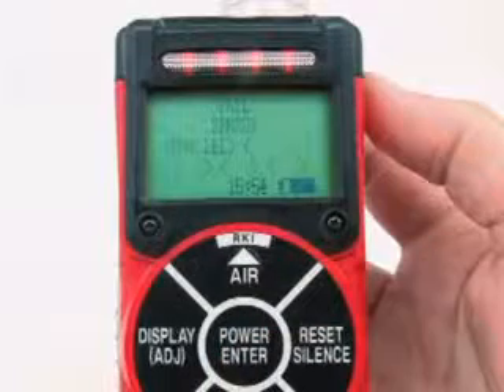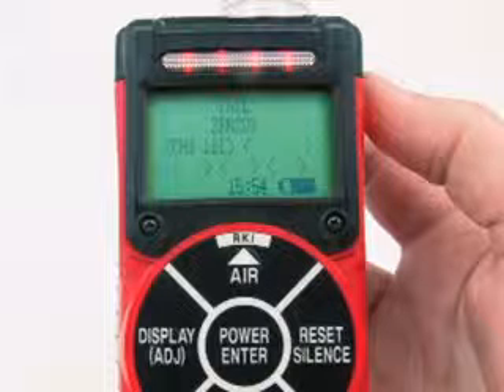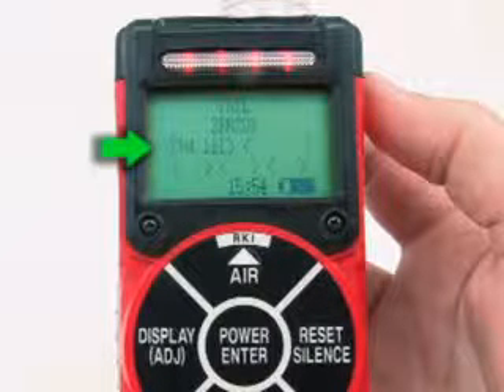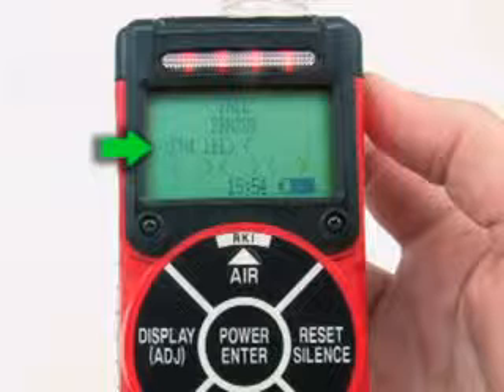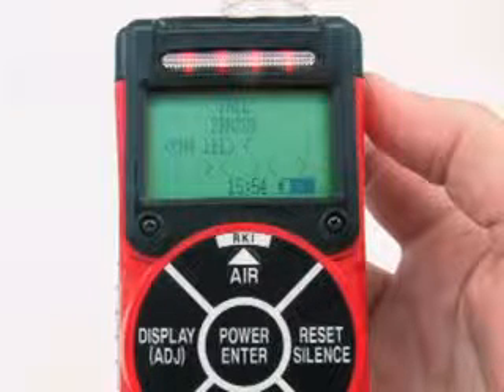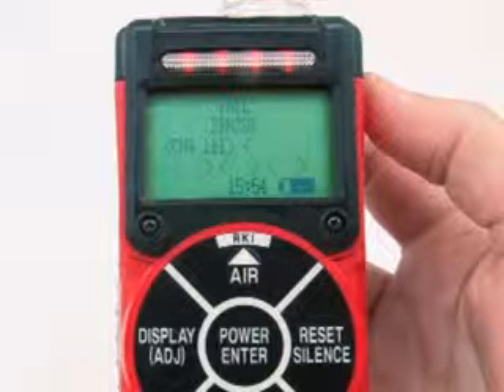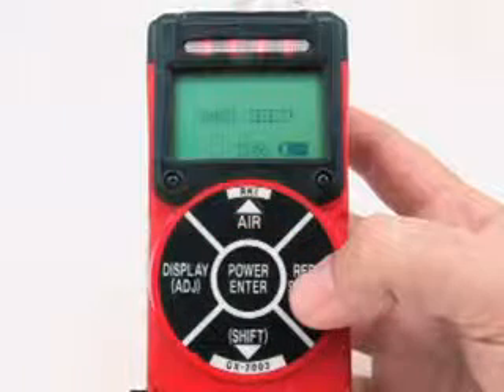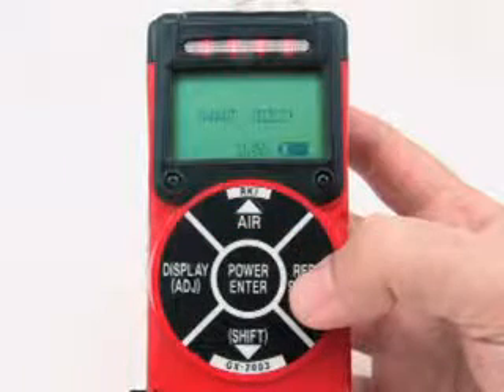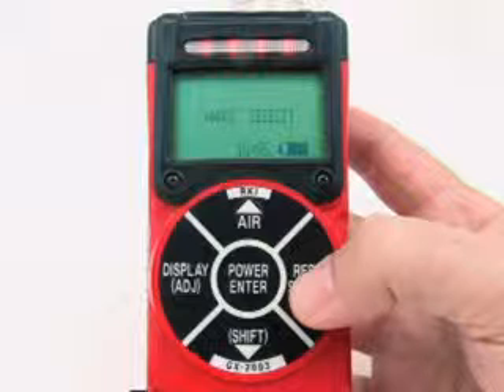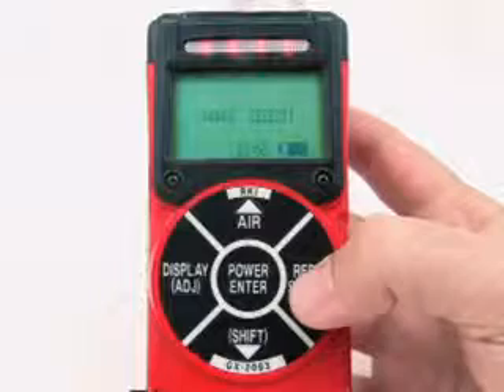If the GX2003 experiences a sensor failure, a screen indicating which sensor failed will display. If one of the combustible sensors, LEL, ppm, or percent volume fails, it is not possible to enter the bar hole mode. Press and release the Reset Silence button to acknowledge the failure and return to the Mode Select screen. Replace the failed sensor as soon as possible.